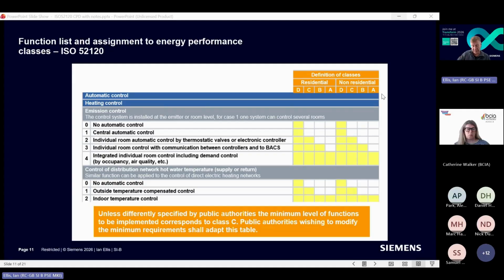Or another good thing for us in the industry is if someone's got an existing building, I can use the standard to do an assessment of what level of control is in there now. And rather than do what sometimes happens when people do an upgrade of a BMS, I'm not saying it always happens, but you might change the old proprietary controllers to a BACnet controller. You might change the room sensors. Siemens, you may know, took over Landis & Gyr. We used to have some that were quite in vogue in the 80s, brown room sensors, which probably are not to today's modern tastes. People change the room sensors to the new snazzy looking ones that we have now, but they don't necessarily take the opportunity to look at the control strategies within that building and say, could something better be done in terms of level of control?